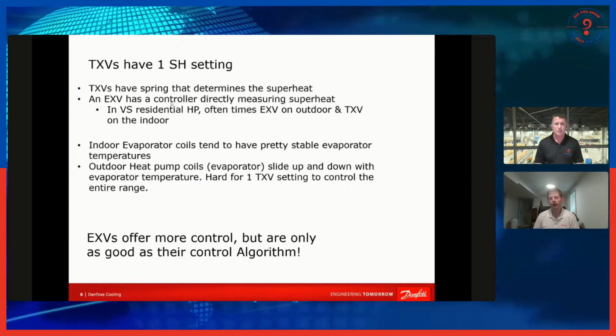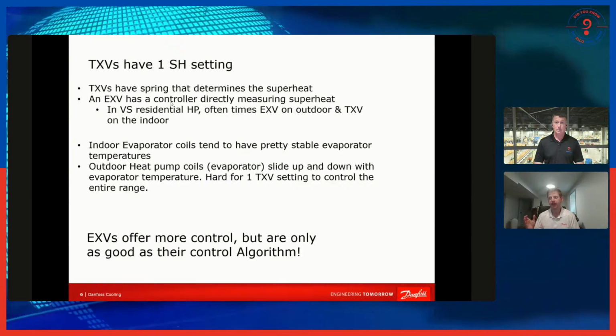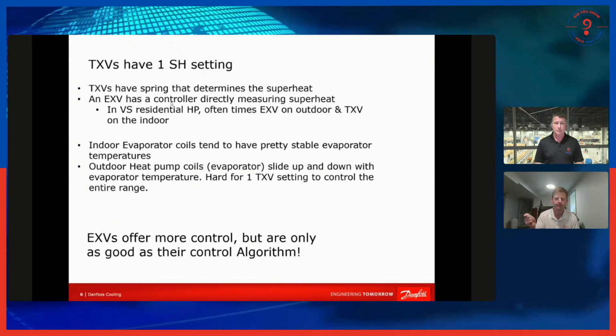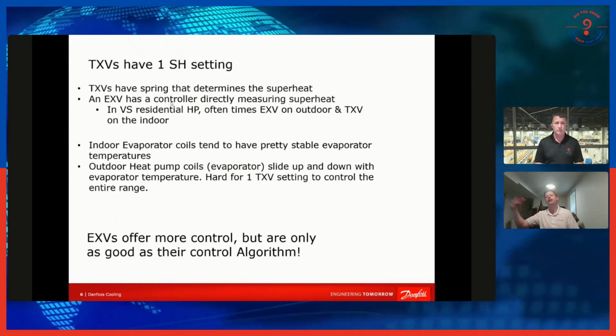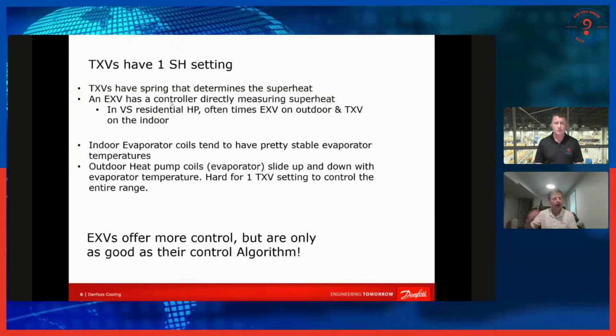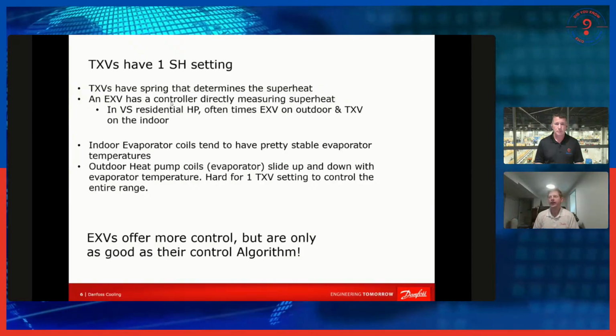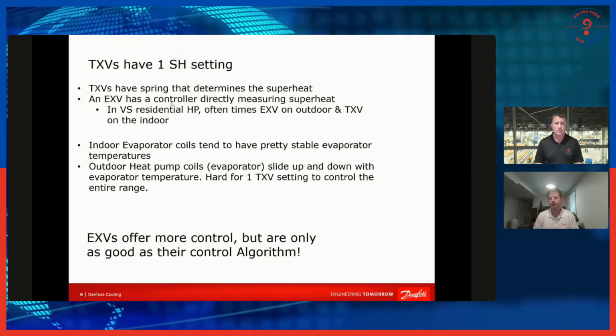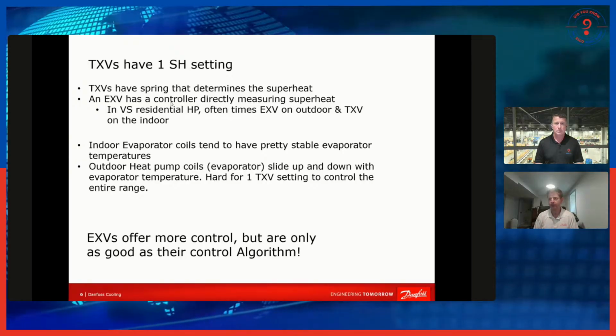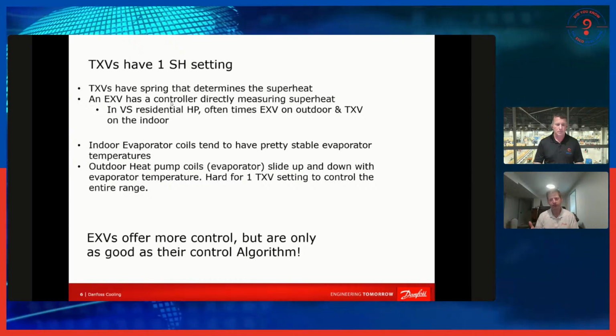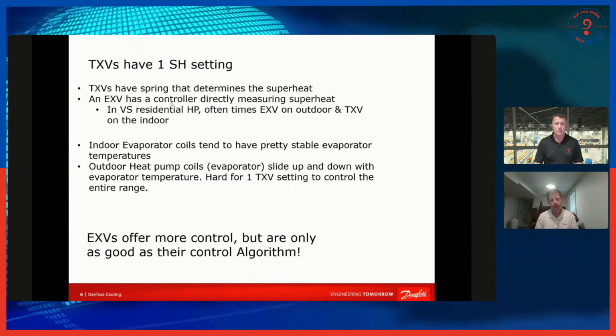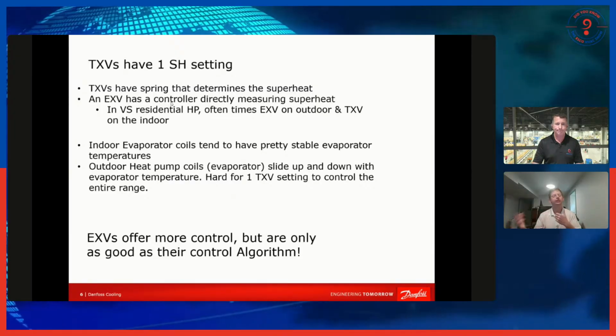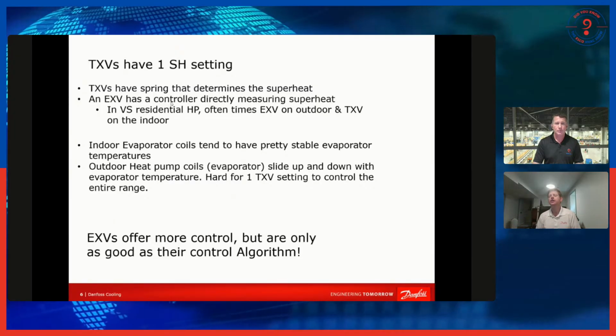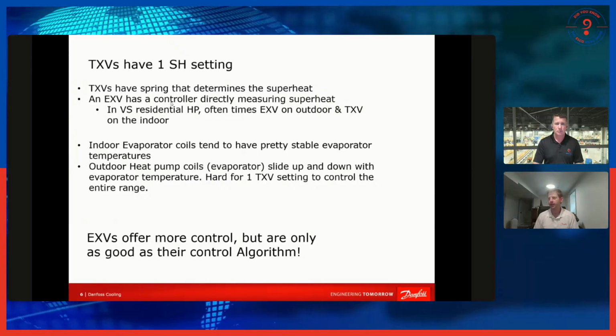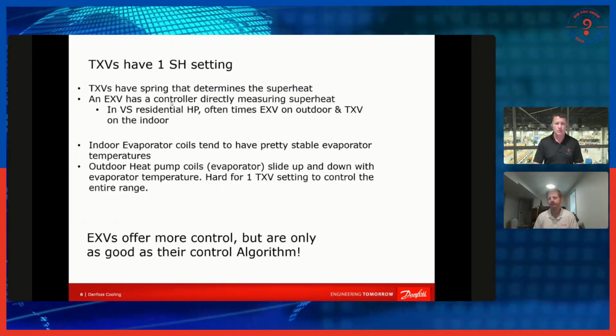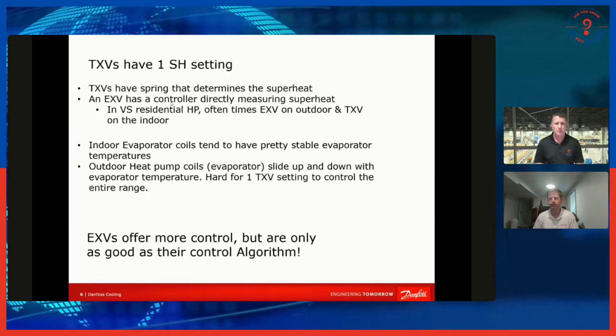And it can make for a much more efficient system, instead of having a TXV that just has one setting and now has to try and manage over this wide range of evaporator temperatures and a wide range of compressor speeds too. So it gives an opportunity for an EXV to be a big advantage in those types of applications. However, they are only as good as their algorithm. It takes a lot of effort on the manufacturer's part to write a good program and to test it and make sure it works as intended. So there are some trade-offs there, but they do have the ability to be a lot better given the resources.